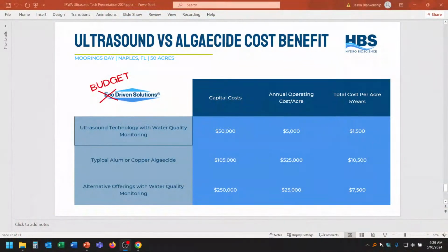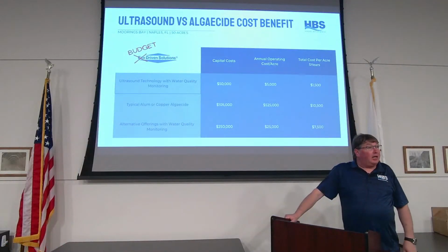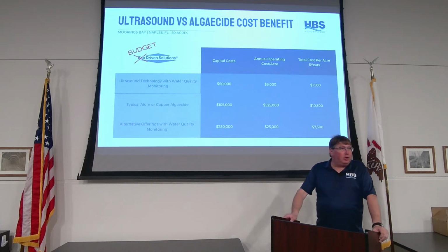Yeah. Do you recommend these are only operated because we have colder temps in the winter? Do these only need to be operated from the spring to the fall? Well, with algae, you don't get as much algae in the winter. So when that water temperature rises, if it doesn't freeze solid, I run them year round, 24 hours a day. Power consumption on these is very, very low. Our owner, an engineer, is very big on efficiency. So it's like running a 60-watt light bulb all day.